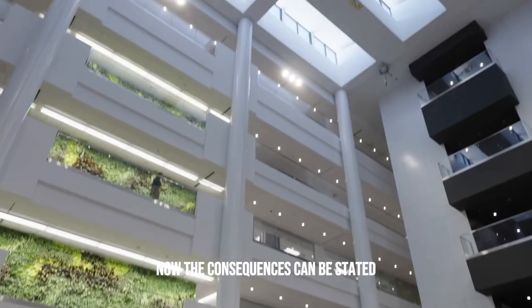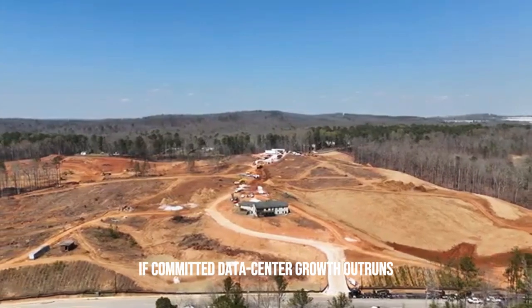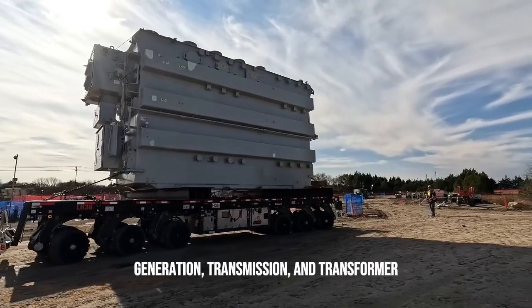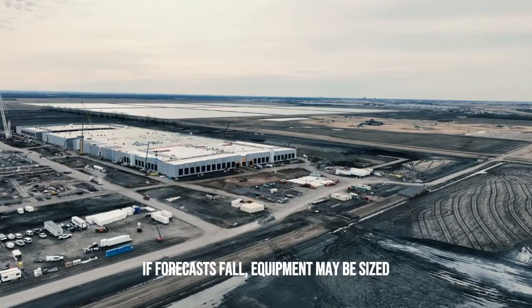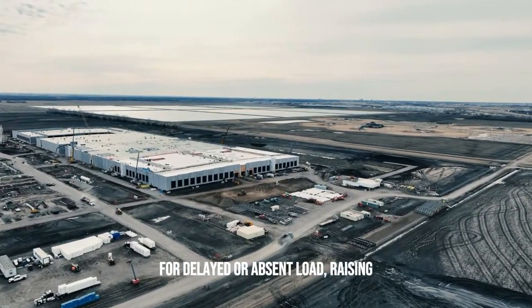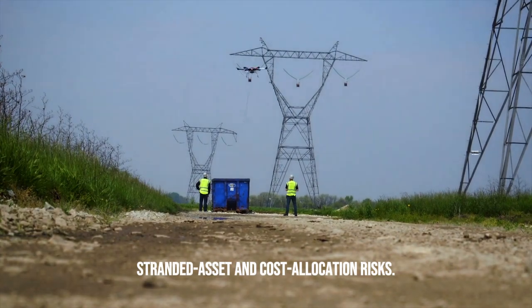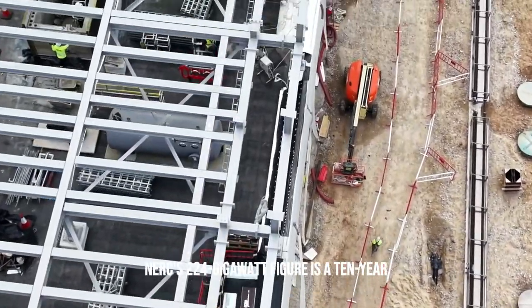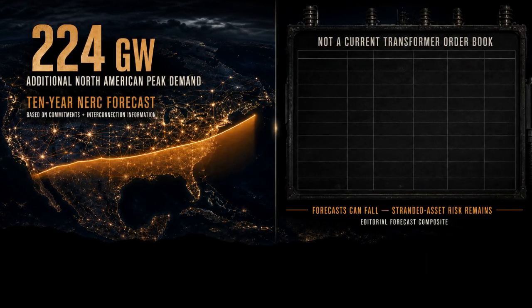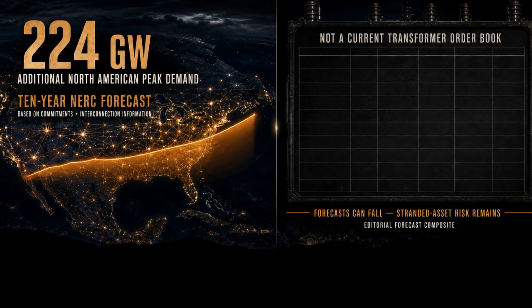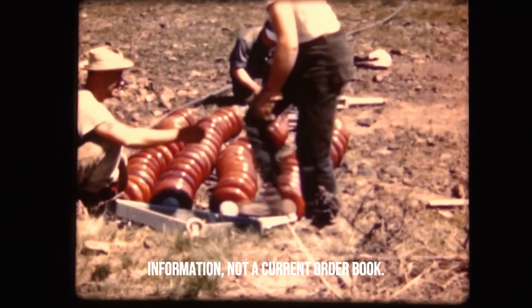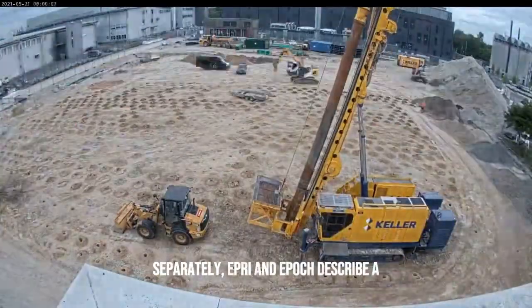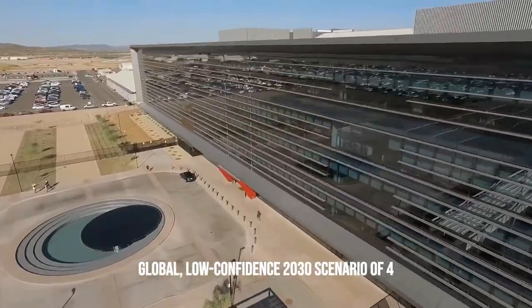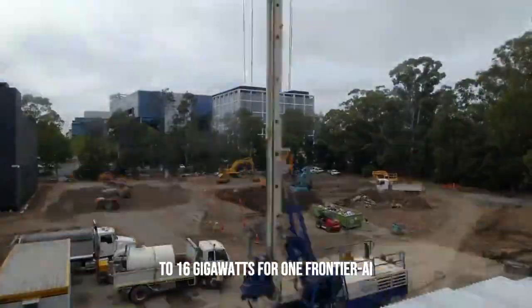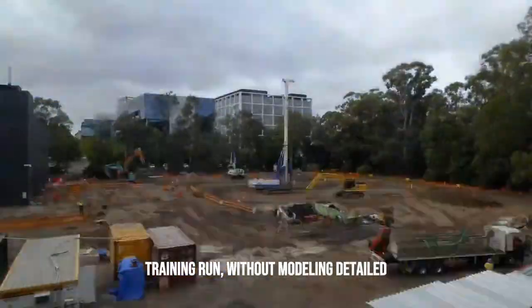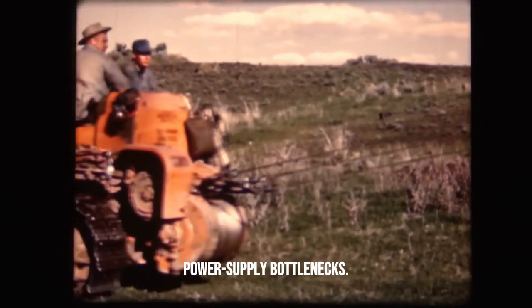Now the consequences can be stated without apocalypse. If committed data center growth outruns generation, transmission, and transformer delivery, chips may be ready first. If forecasts fall, equipment may be sized for delayed or absent load, raising stranded asset and cost allocation risks. NERC's 224 gigawatt figure is a 10-year North American peak demand forecast based on commitments and interconnection information, not a current order book. Separately, EPRI and EPOC describe a global, low-confidence 2030 scenario of 4 to 16 gigawatts for one frontier AI training run, without modeling detailed power supply bottlenecks.